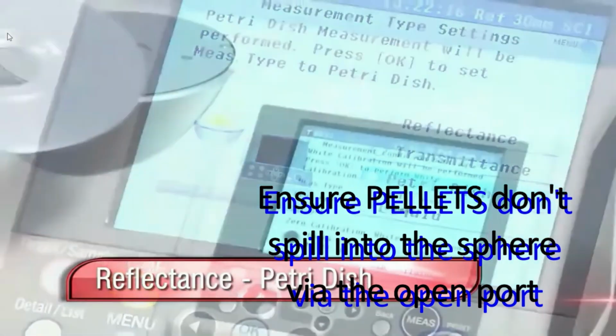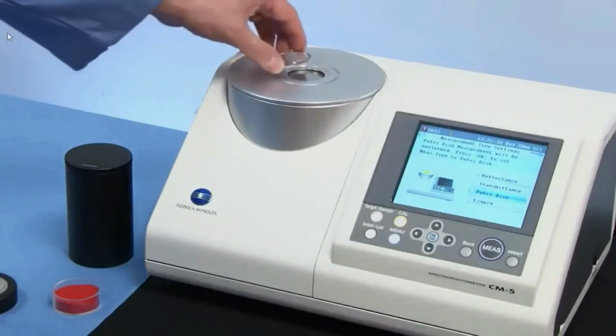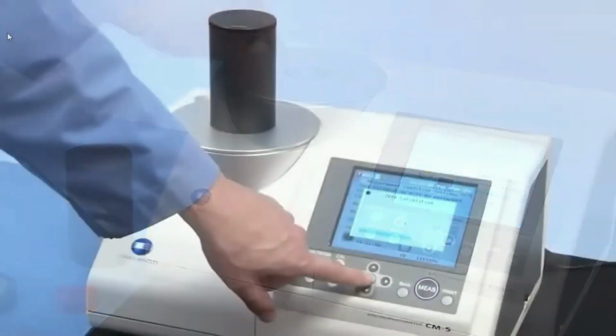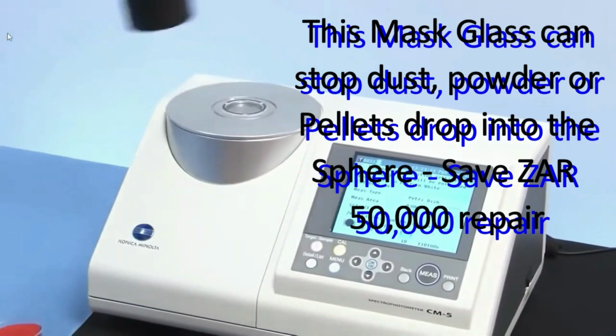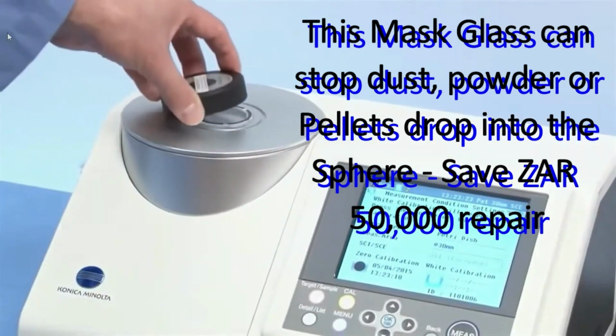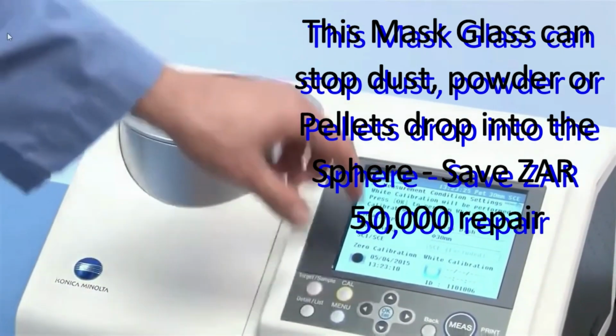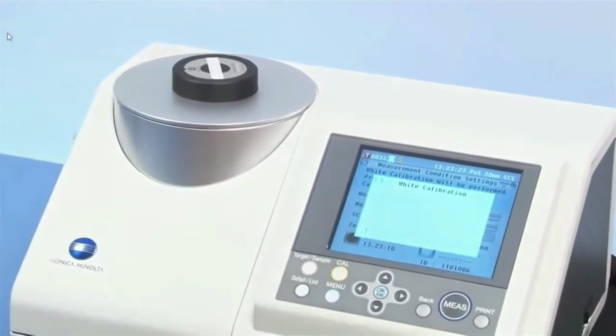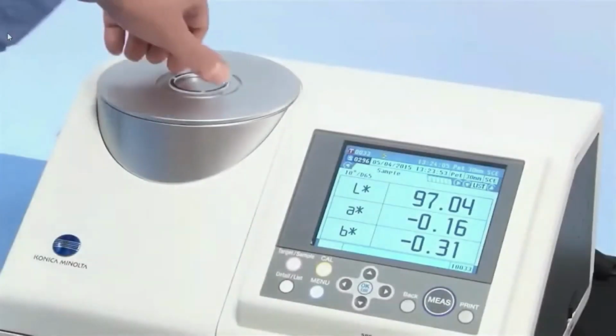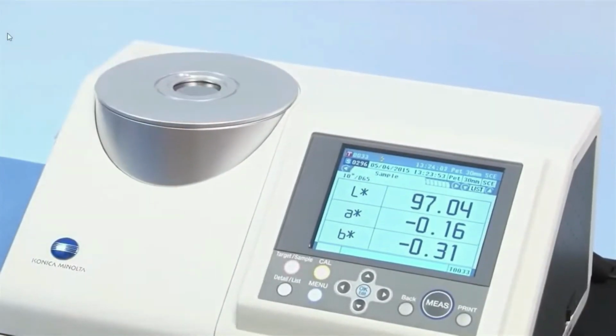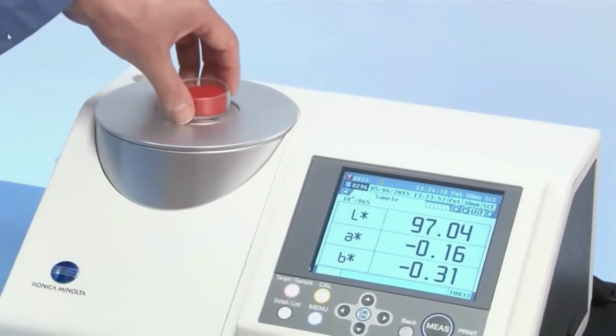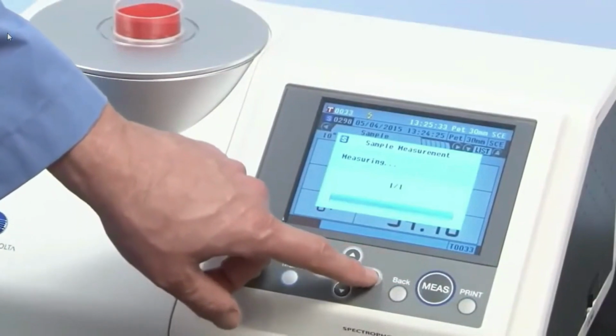To perform a reflectance measurement in Petri dish mode, put the special target mask in place followed by the glass accessory piece. Perform zero calibration and then an external white calibration through the glass piece. This will normalize the instrument when measuring samples through a Petri dish. Proceed to measure your targets and samples in reflectance mode as normal.